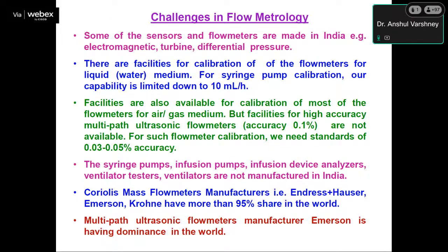What are the challenges in flow metrology? Some of the sensors and flow meters are made in India, like electromagnetic, turbine and differential pressure meters, and the performance of these meters is not verified in terms of their accuracy and repeatability. There are facilities for calibration of flow meters for liquid medium. For syringe pump calibration, our capability earlier was from 10 ml, and now it is from 1 ml per hour. We are not providing calibration below 1 ml per hour.